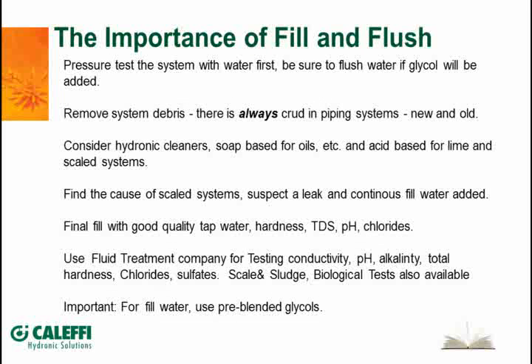You'll see the drip on a threaded joint or on a flange connection where you haven't tightened the bolts or something like that. And like I say, you want to get the dirt and debris out of the system, and there's always dirt and debris in systems, regardless of a brand new system that you put in. I know here in Missouri we get these little wasps. They're called mud daubers, and they'll build little nests in any tube that you don't have a cap on or a piece of tape over the end of it. These things get in there and they build a little nest, and of course that's going to flush through to your system.